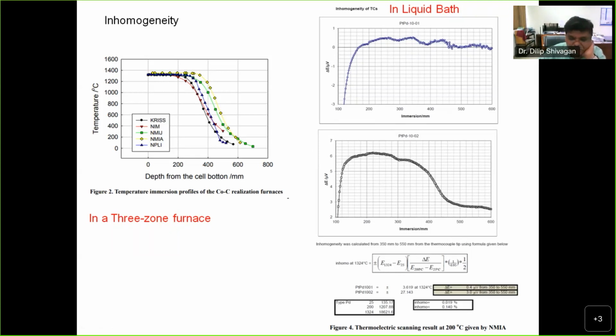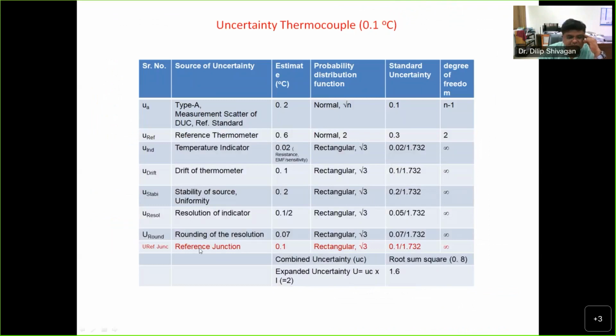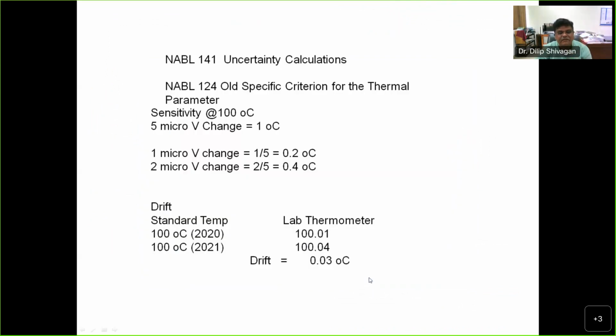So always you have to take out the thermometer as it is getting cold, otherwise its properties will quench. You don't know what is happening, but the level of inhomogeneities are quite large, and you never get reproducible measurements. So the reference junction here is very important, and the inhomogeneity of that thermocouple in this case.